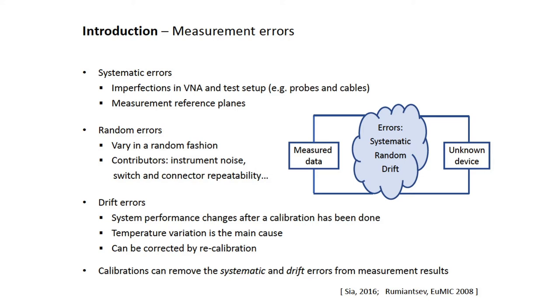There are also random errors associated with the measurement data — they vary in a random fashion. Contributors include instrument noise, switch, and connector repeatability. There are also drift errors — for example, system performance changes after calibration has been done. Usually a temperature variation is the main cause. These drift errors can be corrected by re-calibration.